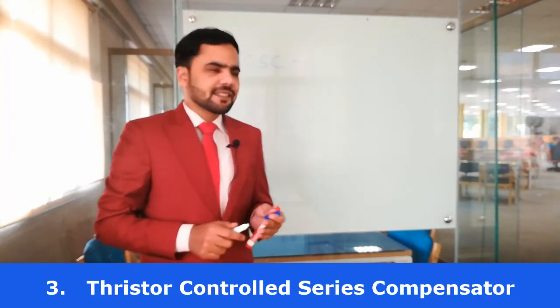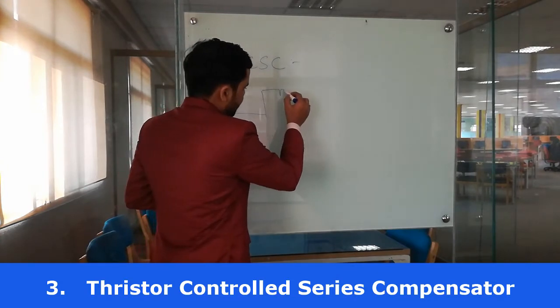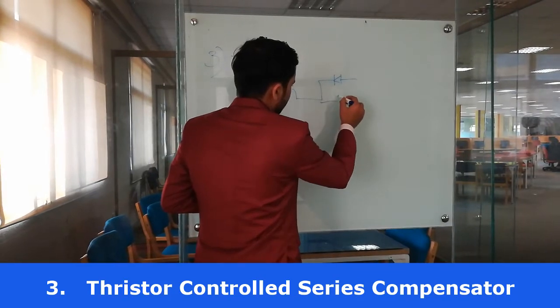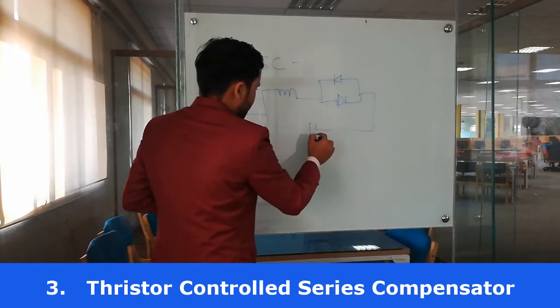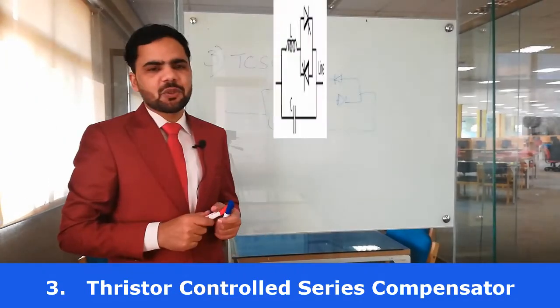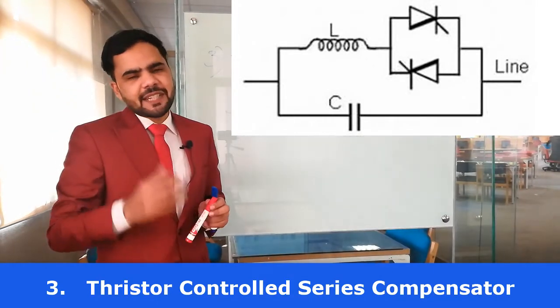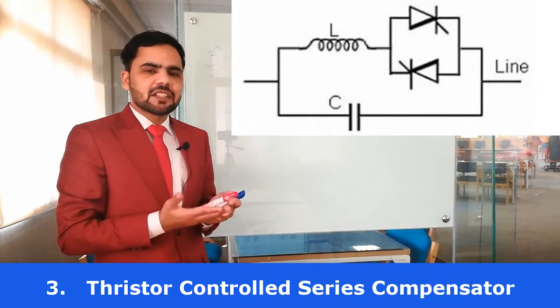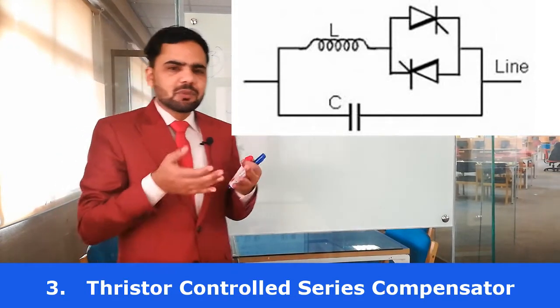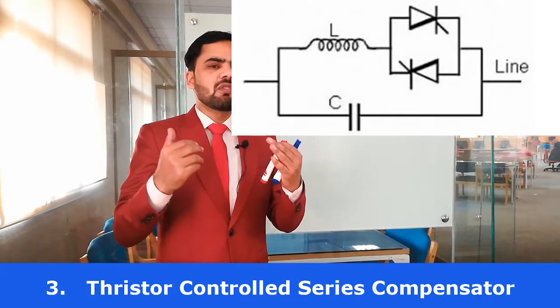The basic working principle is that it consists of a capacitor bank in parallel with a thyristor controlled reactor. The triggering angle of the thyristor controlled reactor decides whether it acts as an inductor or capacitor — whether it generates reactive power, absorbs reactive power, or handles under-voltage or over-voltage conditions.